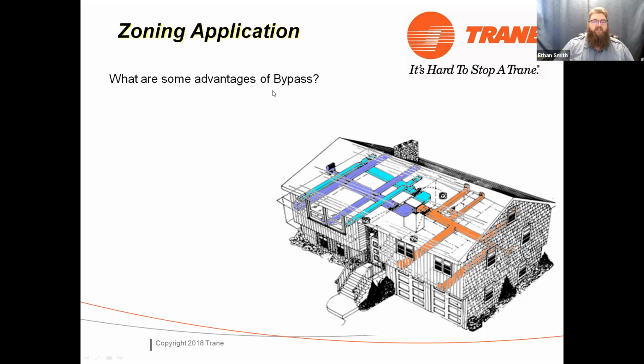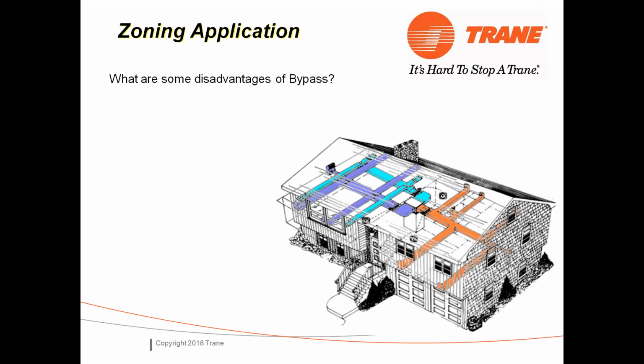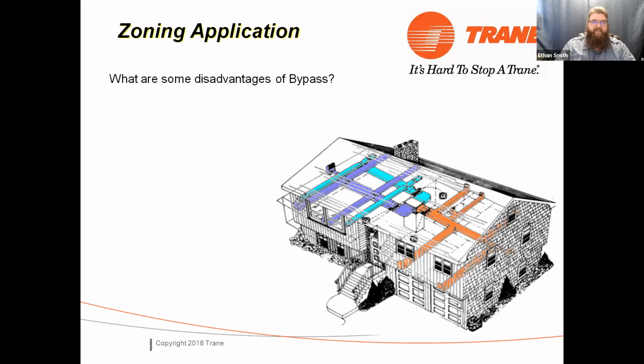There are systems where if you've just got a little bit of bypass, it might work out okay. Any big disadvantages to bypass you guys can think of? Waste money. Okay. They can be an efficiency loss, either through short cycling the equipment or not delivering capacity into the space. Can it cause noise issues? Yes, they can. Improperly applied bypasses can make your equipment very loud. Any others? We mentioned Larry. I think Larry's comment can be put into both categories of does shorten your equipment life.